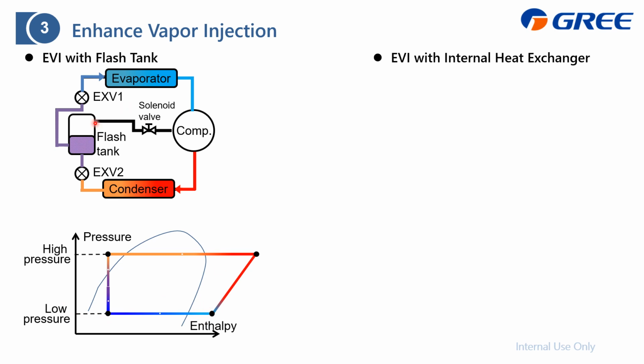And here we just inject from this solenoid valve, which is to get the saturated refrigerant, which is from here, to inject into the compressor. And from the log P-h diagram, it will become this one. This will lower the compressor discharge, just like this. And also it can raise the high pressure. Besides, also it can extend the evaporator range to raise the capacity.